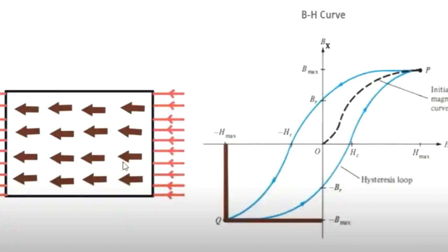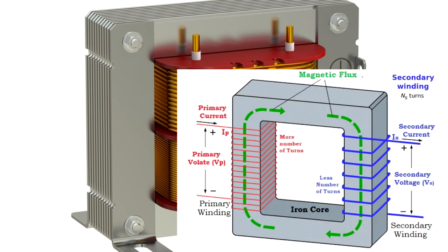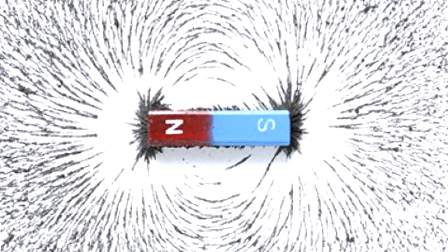In normal operation, our transformer is going to be fed from an AC supply, and so the current in the transformer is going to be going in a forward direction and then a reversing direction 50 times a second, because that's the frequency of the mains in the UK. Now, because our current is alternating, the magnetic flux which we are raising within the transformer will also be going forward and in a reverse direction 50 times a second. Now I'd like you to imagine that you're part of the core material of the transformer, so let's imagine that you're a molecule. And when the current is flowing in a positive direction, you're going to align yourself with the north pole of the magnetic field. Now when the magnetic field reverses, you're going to turn around and face in the south direction. And you're going to turn round 50 times a second as the magnetic field reverses.